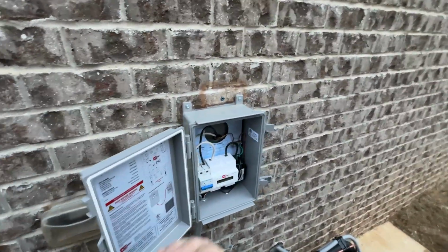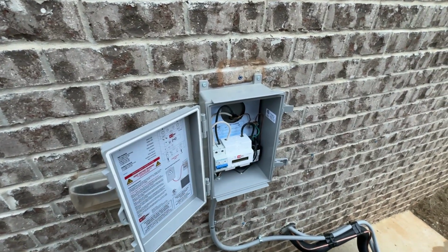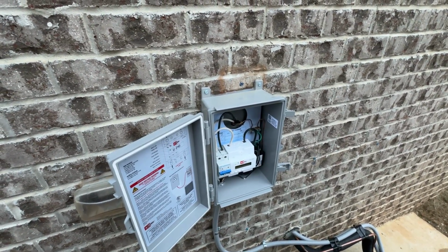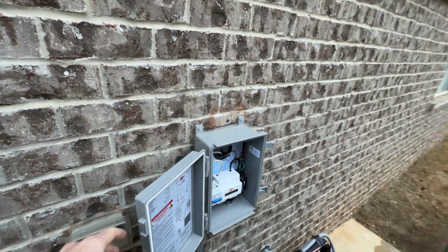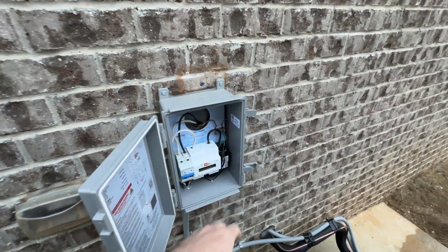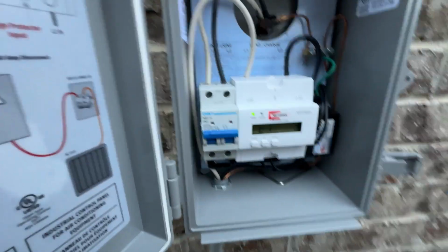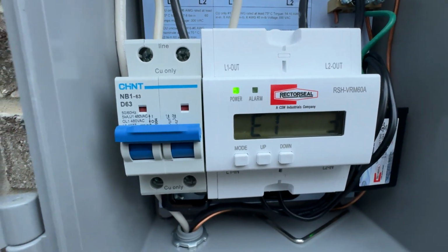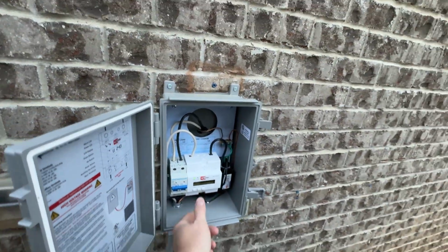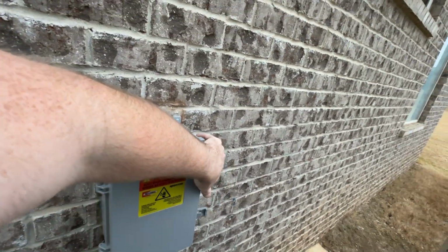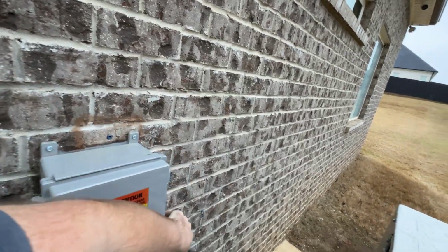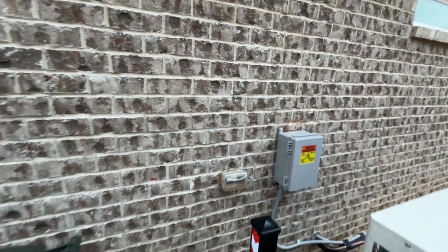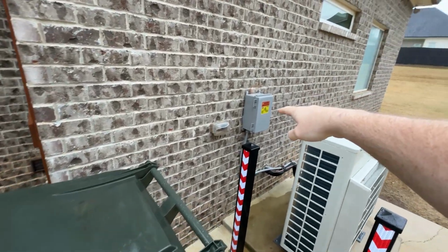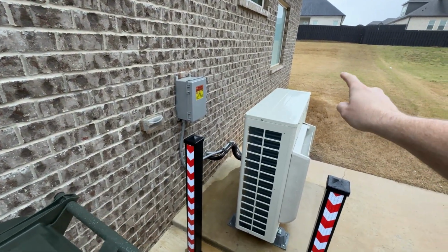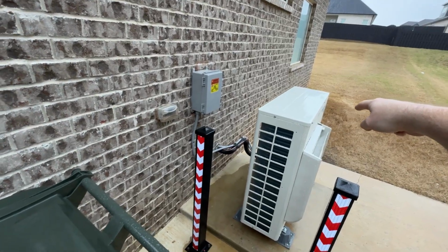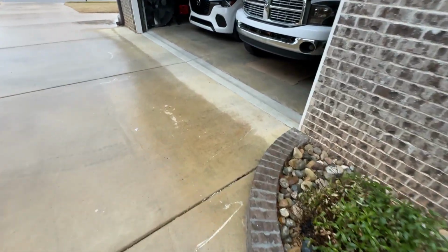Hallelujah. And so on this thing, they calibrated it twice. 2 different electricians came out from Conditioned Air, and so I knew this was correct. The first time I called the utility company yesterday morning, this had tripped. We had an alarm, and you can see, I'll hit the up arrow here. Code E1, 3 events. And what that's telling you is that this thing tripped 3 times, which means it detected electricity in excess. They had it set for 253 because you want it to turn off. You want that surge protector to trip before this one trips, because this is not designed to do that. It will do it, but it's not designed to do it. So you want that to trip.